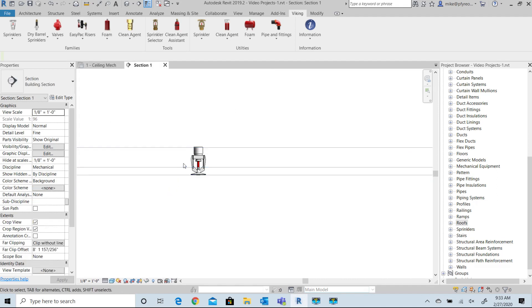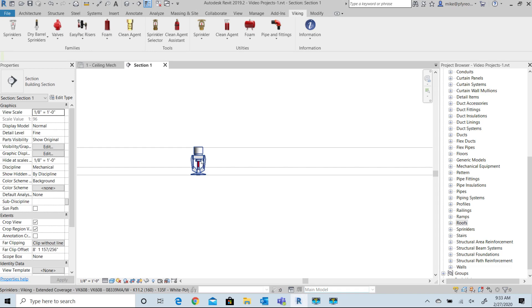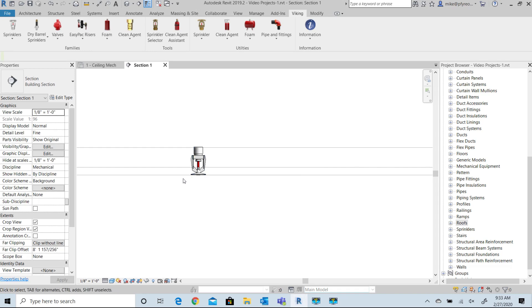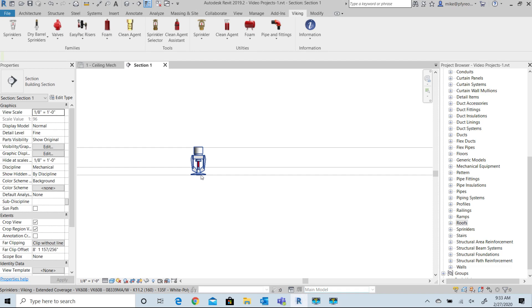Now view the sprinkler from a section view to make sure that you've set the values correctly for this family. You will see the eight foot ceiling and the sprinkler has been inserted at eight feet. The insertion point is the deflector for our families.